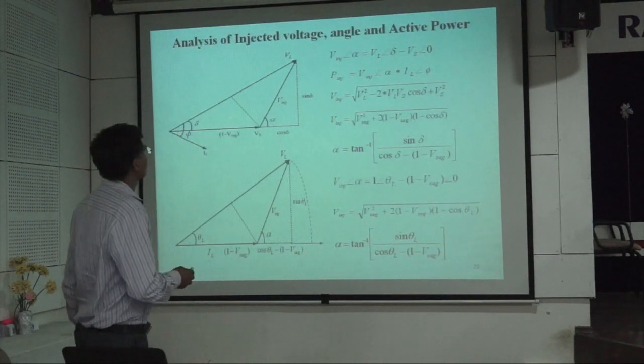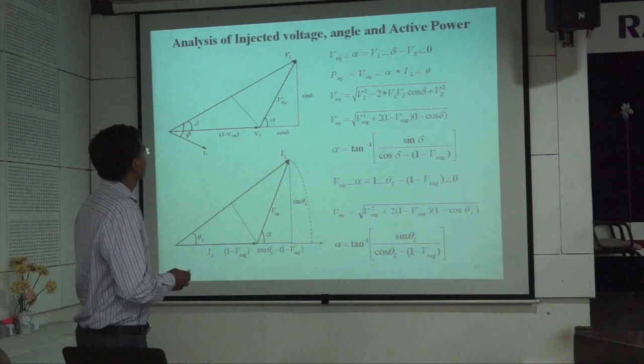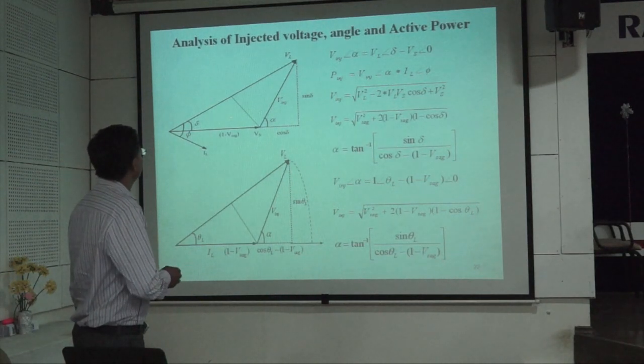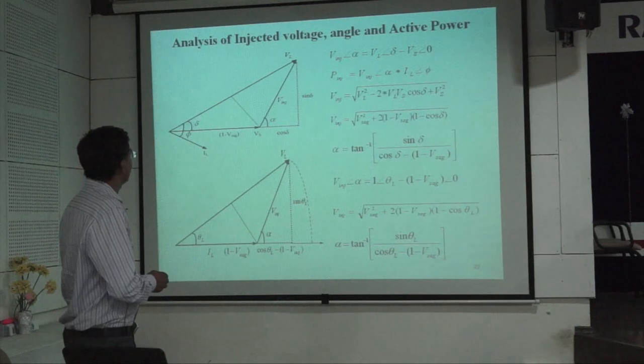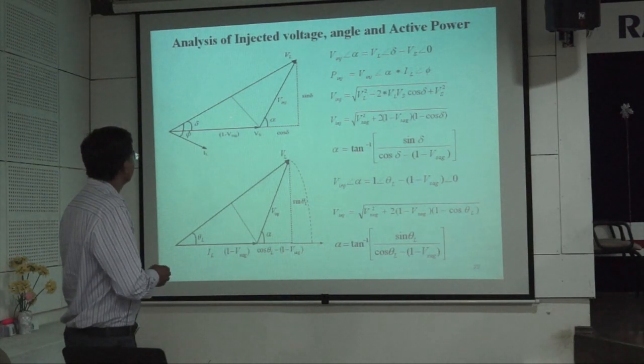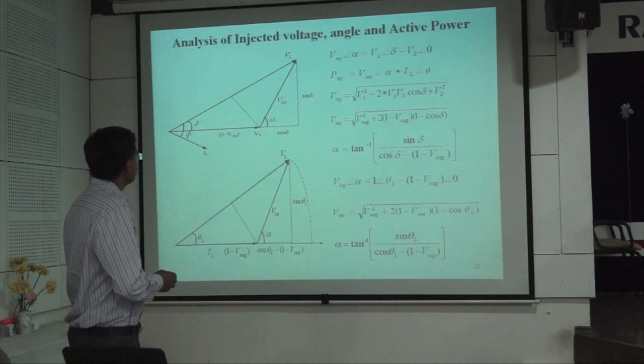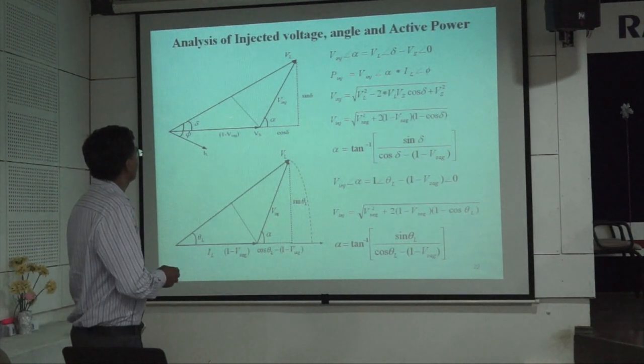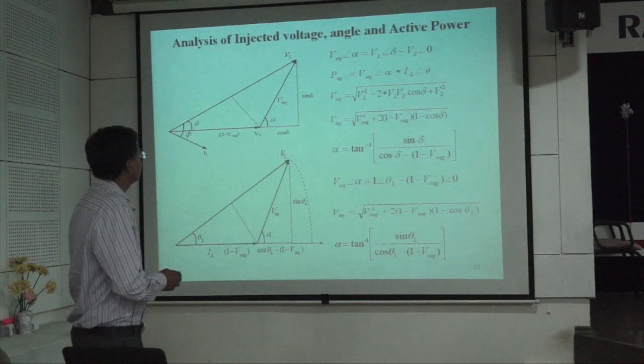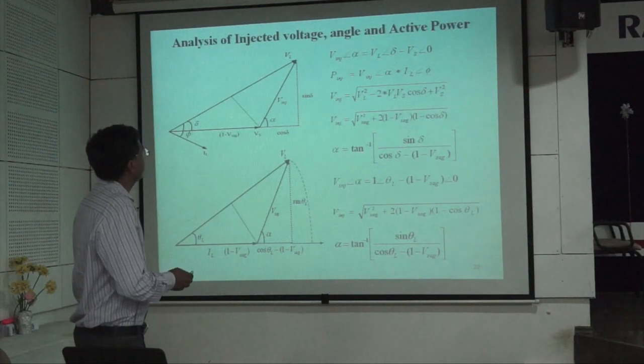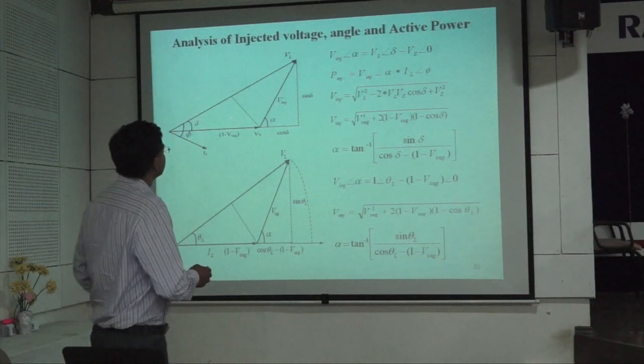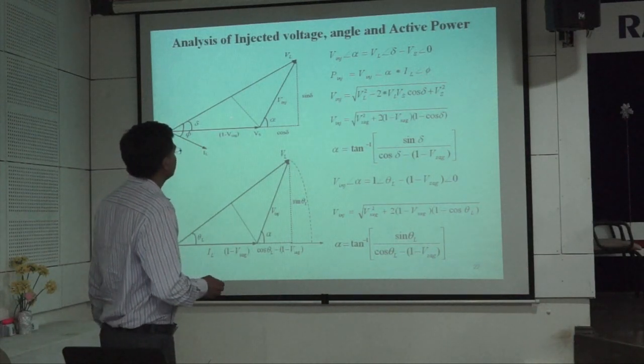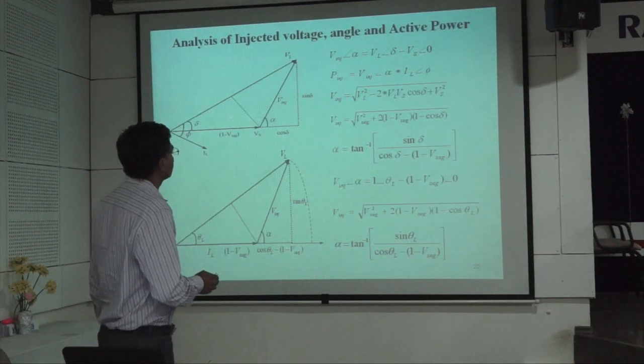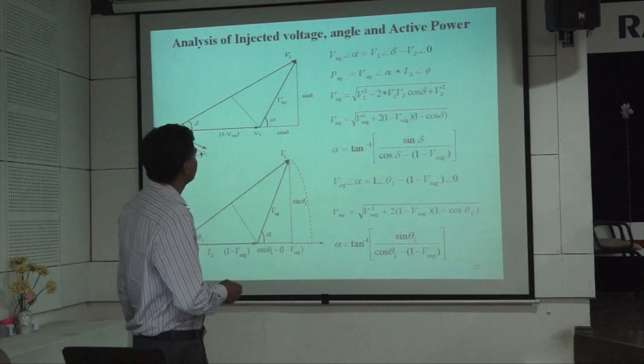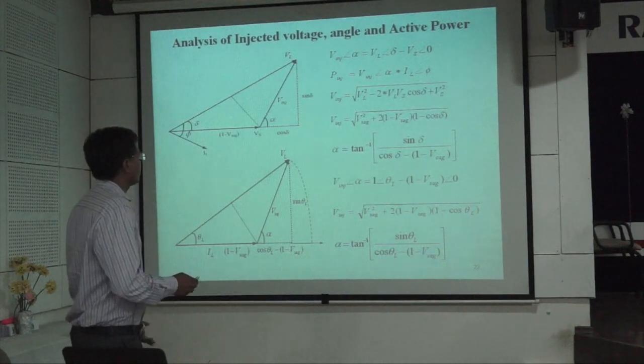Now the analysis for the injected voltage, angle and active power. This is the injected voltage. This is the load voltage. Whenever there is a drop in load voltage or supply voltage, it will jump to a certain angle, and we have to inject at a particular angle alpha. This is the reference axis. These are the equations which govern this. Certain trigonometry has been implemented, and from this V injected and angle injected have been computed.